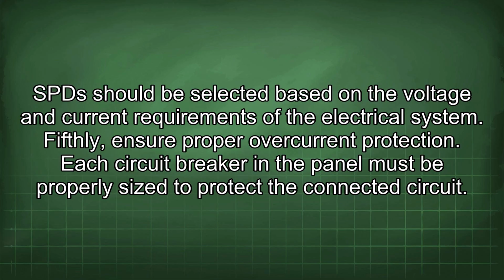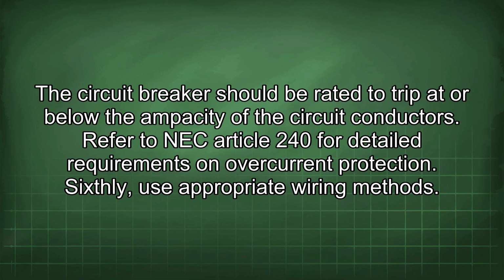Fifthly, ensure proper overcurrent protection. Each circuit breaker in the panel must be properly sized to protect the connected circuit. The circuit breaker should be rated to trip at or below the ampacity of the circuit conductors. Refer to NEC Article 240 for detailed requirements on overcurrent protection.